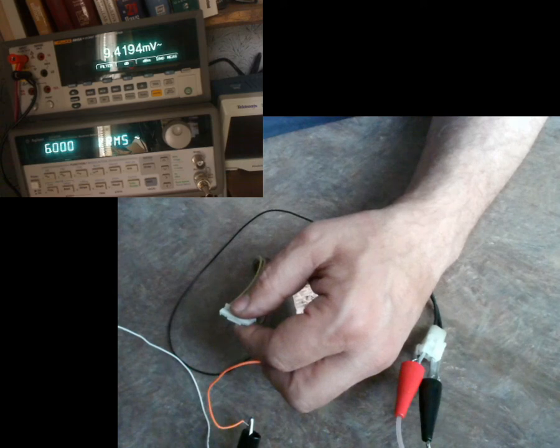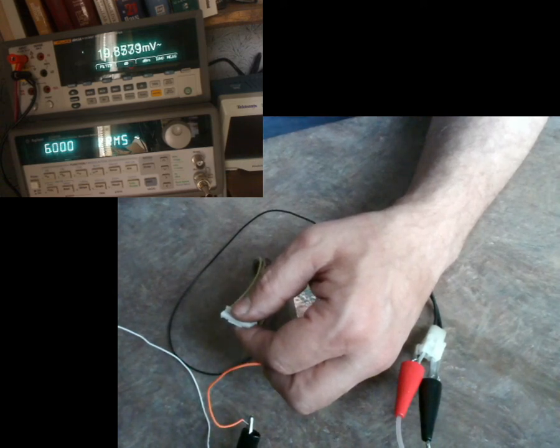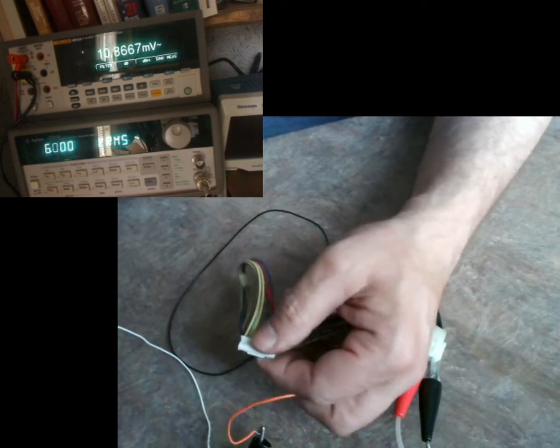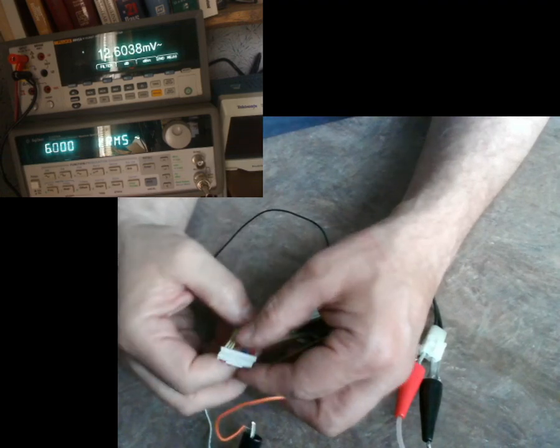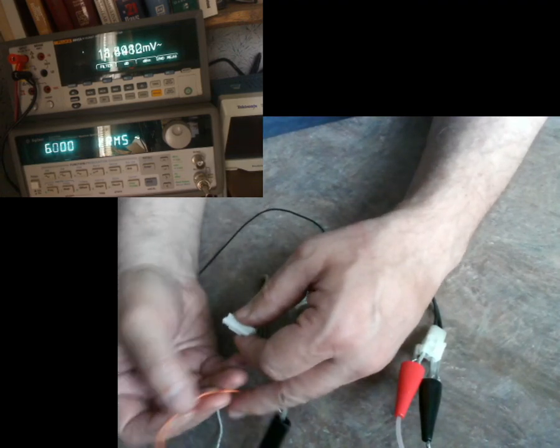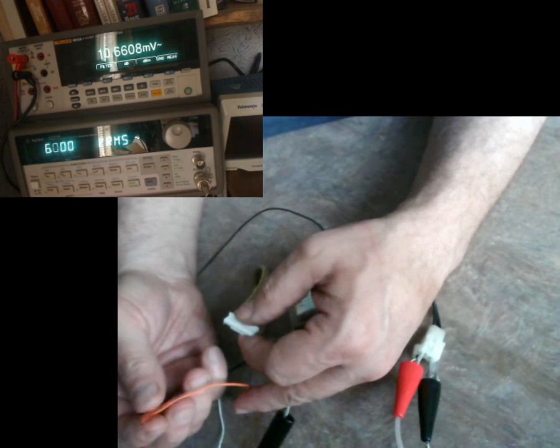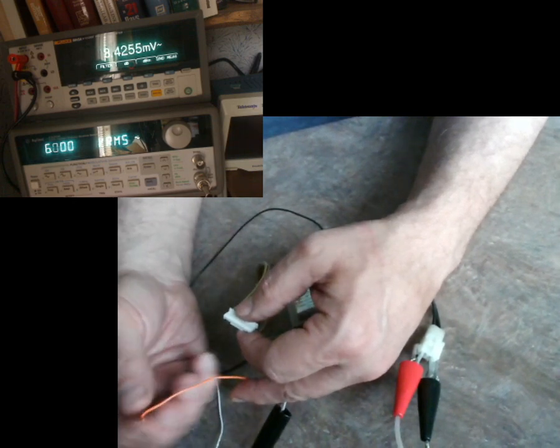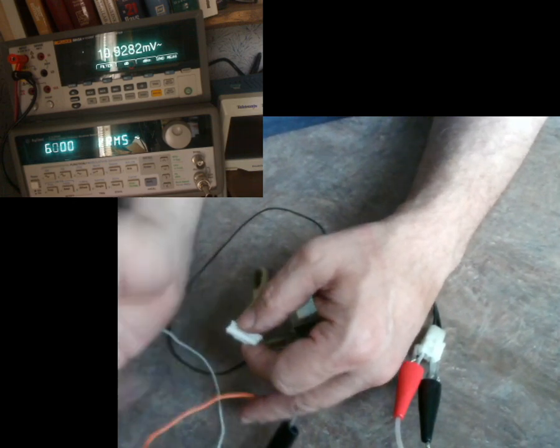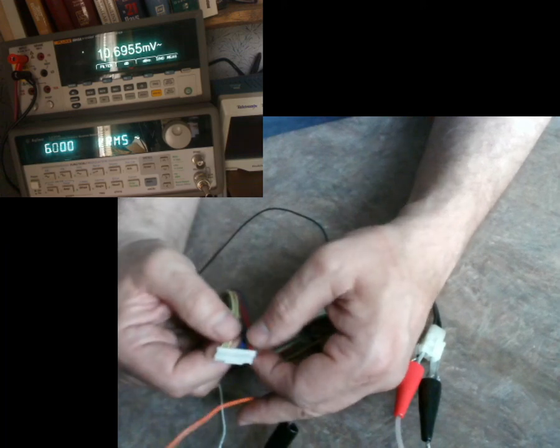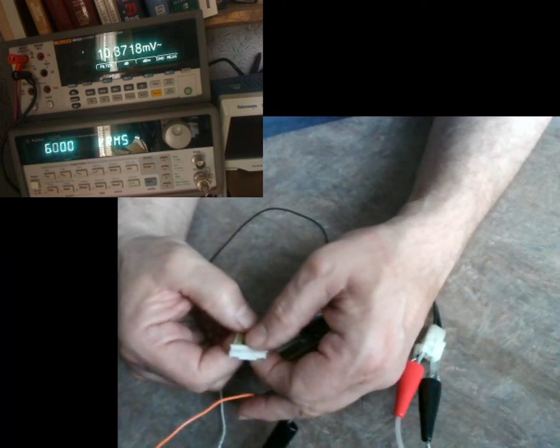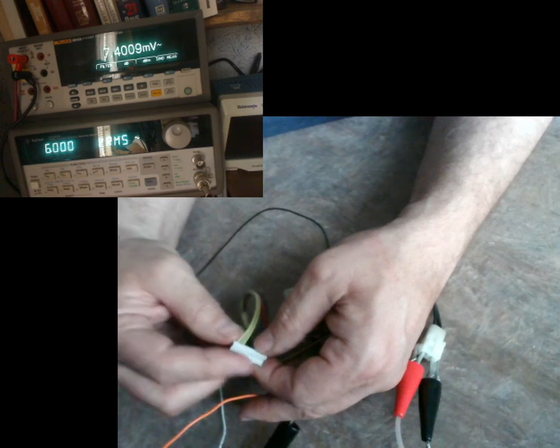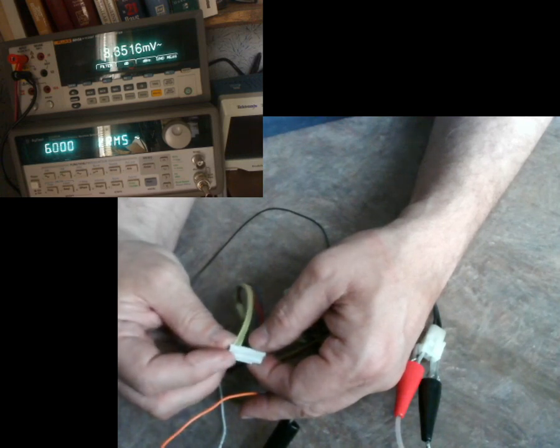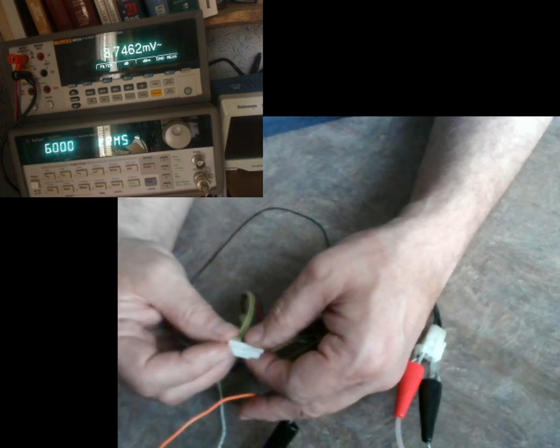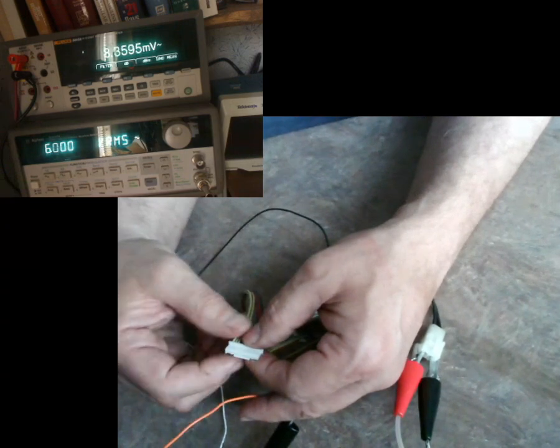Now, I guess I'd want to say one thing: sometimes if you have bad insulation in your transformer, a low voltage test like this may work okay, but once the transformer heats up and is running at full load, it could still actually be bad, because as it heats up and the copper expands, it could be shorting out within some of the windings there.